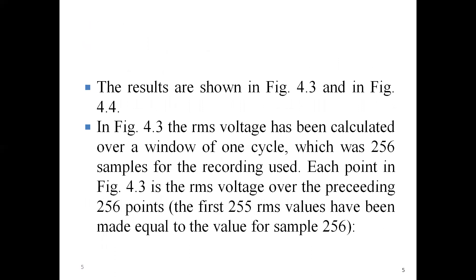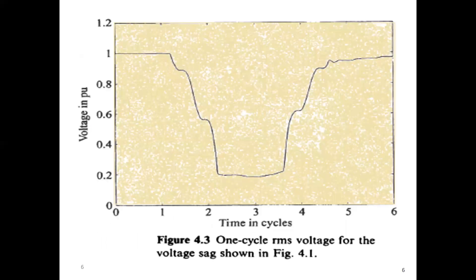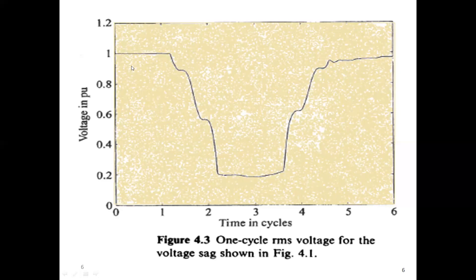Looking at the next figure, we can observe the RMS voltage which has been calculated for a window of one cycle, which has 256 samples for the recording. As the voltage values are recorded through monitors, for one cycle, 256 sample time points are recorded. This is the voltage waveform recorded with the help of 256 samples. Each point in this figure is the RMS voltage for the preceding 256 points, and the first 255 RMS values have been made equal to the value for sample 256.